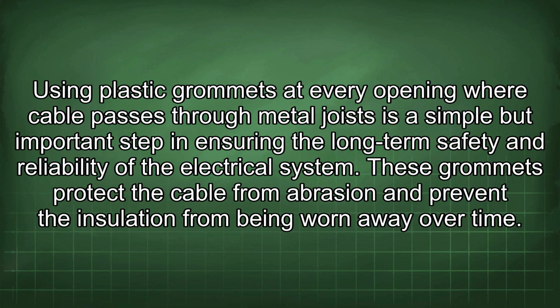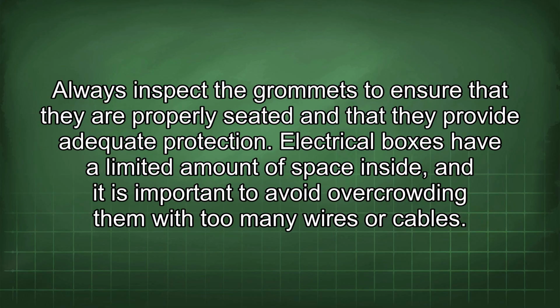Using plastic grommets at every opening where cable passes through metal joists is a simple but important step in ensuring the long-term safety and reliability of the electrical system. These grommets protect the cable from abrasion and prevent the insulation from being worn away over time. Always inspect the grommets to ensure that they are properly seated and that they provide adequate protection.